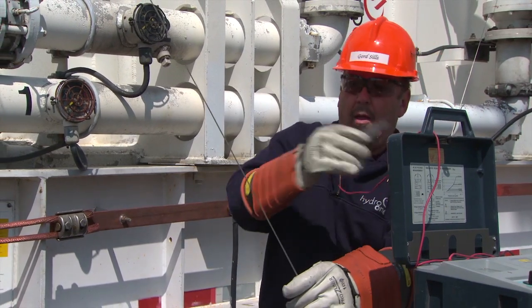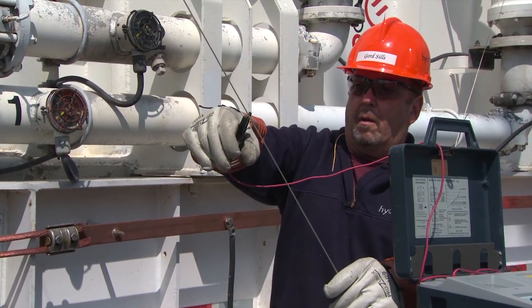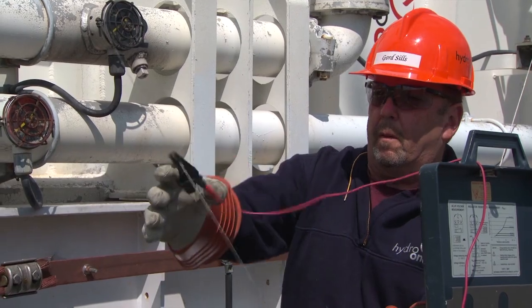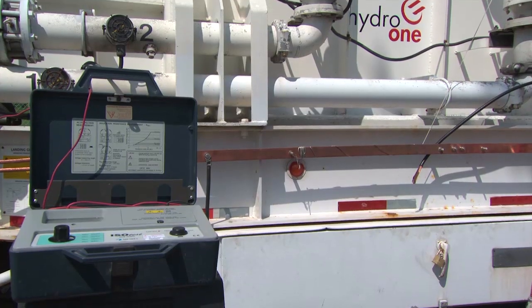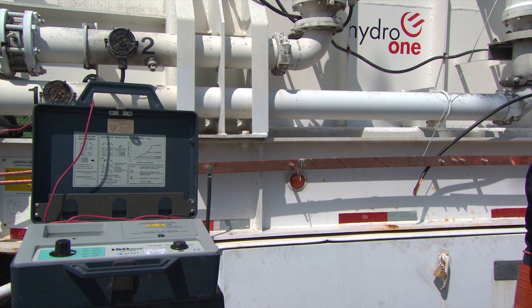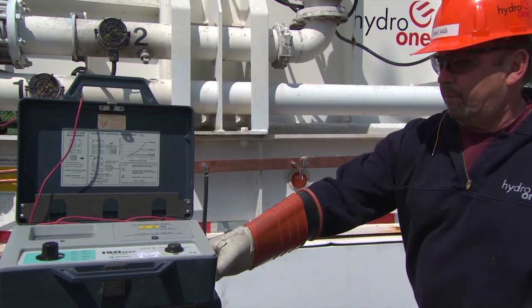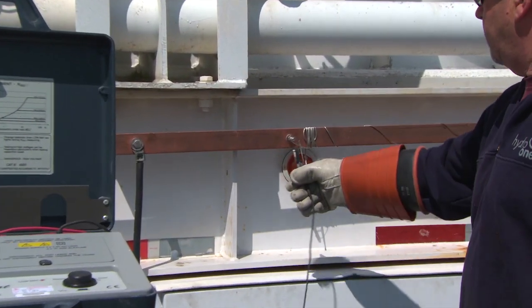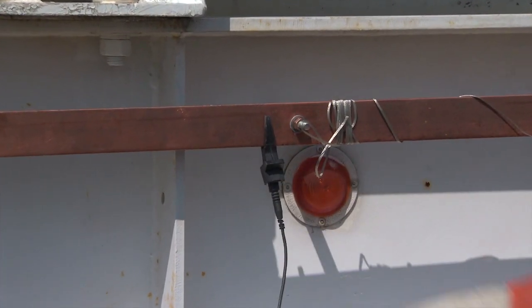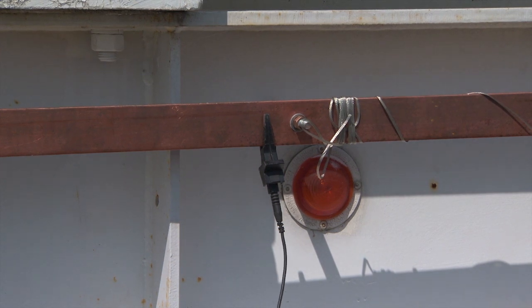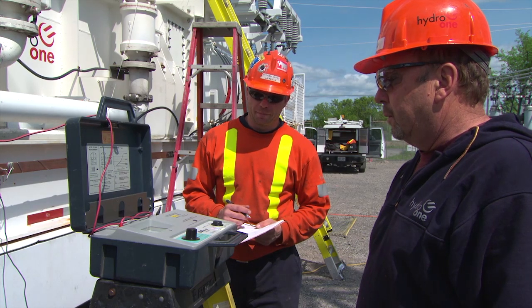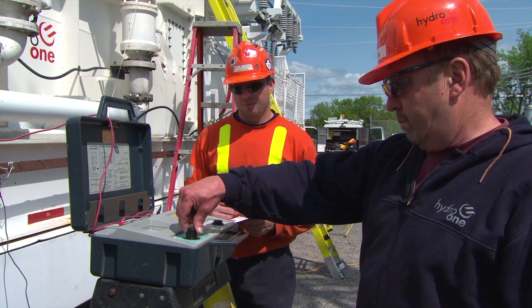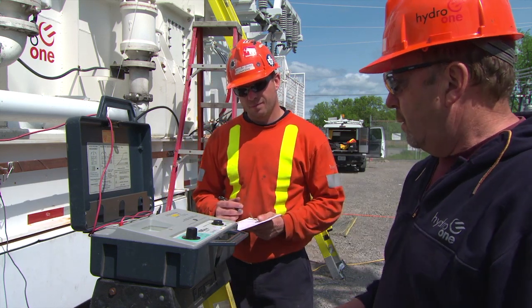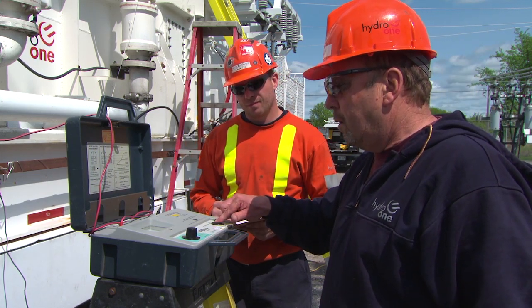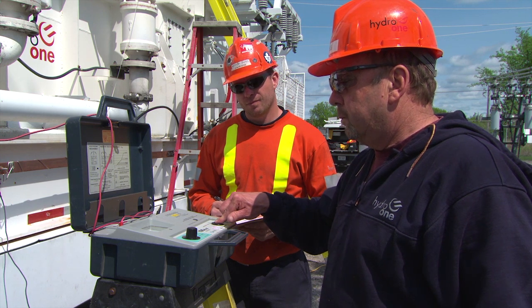In order to test the high-voltage windings to the grounded low-voltage windings, remove the ground from the high-voltage bushings and attach 1 megger lead. Then connect the other megger lead to ground. Ensure all employees are clear of the transformer and perform the test. Record test results and then ground the high-voltage bushings.